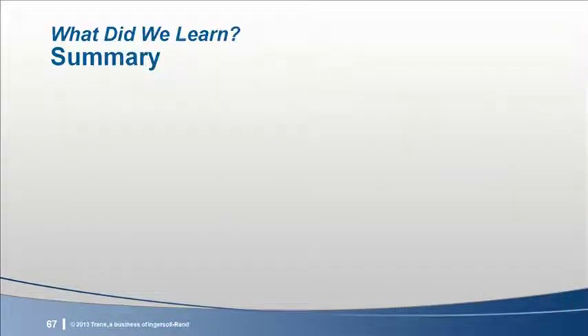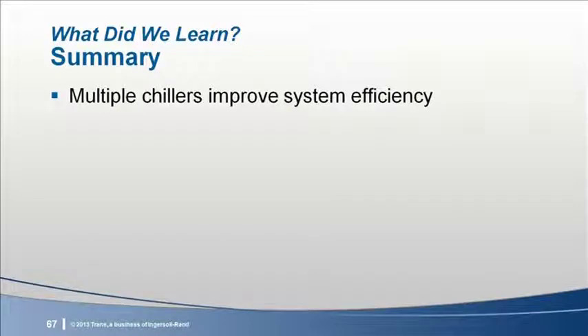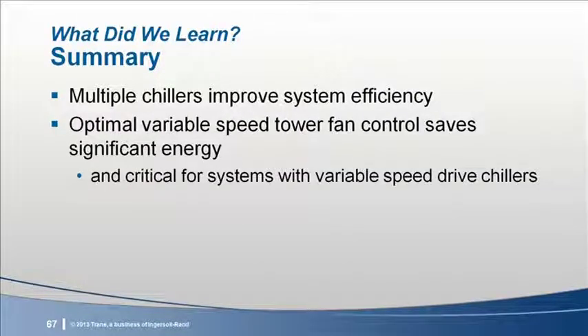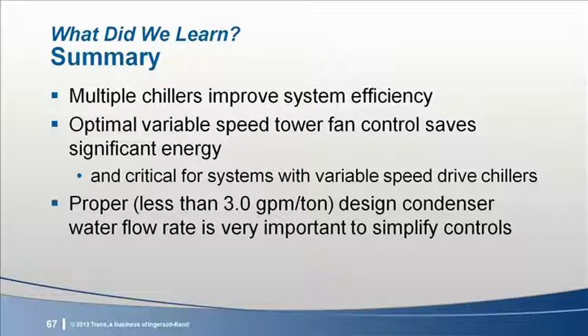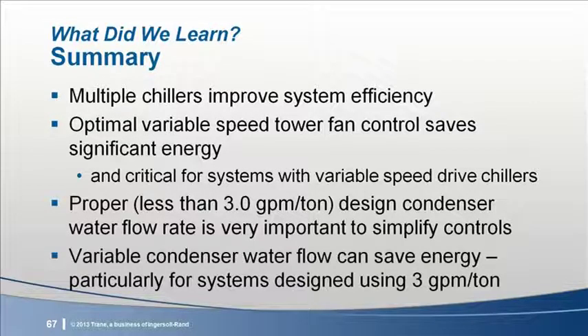So let's summarize all the conclusions. Multiple chillers improve system efficiency. Optimally controlled variable speed tower fans save a lot of energy, and that control is absolutely critical if variable speed chillers are applied. Proper design condenser water flow rate is important and allows simple condenser water control. And variable speed condenser water pump control can save some energy, but primarily on over-designed systems.